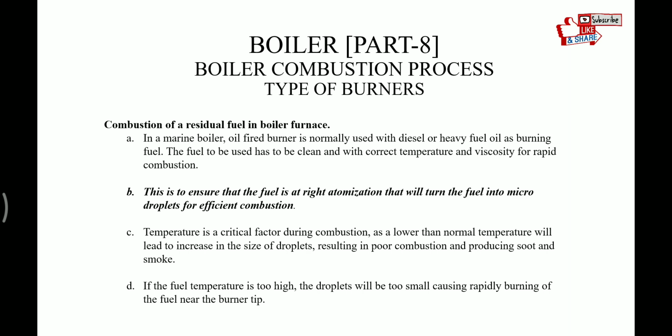Temperature is a critical factor during combustion, as a lower than normal temperature will lead to an increase in the size of droplets, resulting in poor combustion and producing soot and smoke. If the fuel temperature is too high, the droplets will be too small, causing rapid burning of fuel near the burner tip.